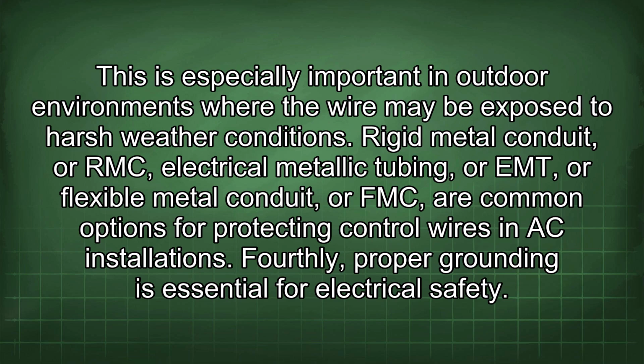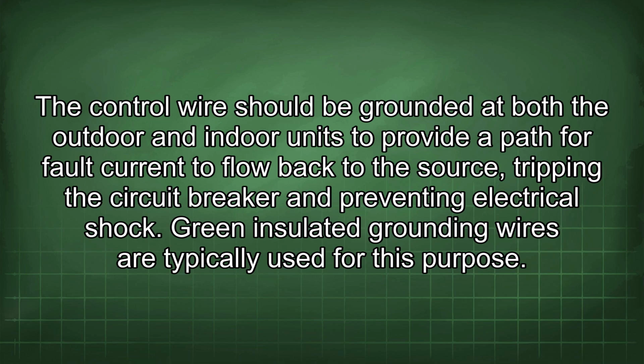Fourthly, proper grounding is essential for electrical safety. The control wire should be grounded at both the outdoor and indoor units to provide a path for fault current to flow back to the source, tripping the circuit breaker and preventing an electrical shock. Green insulated grounding wires are typically used for this purpose.